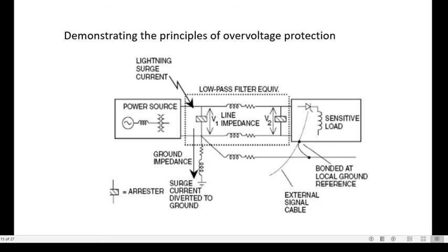So this metal oxide varistor acts as an insulator at a nominal voltage, and at an increased voltage due to lightning, it acts as a conductor, diverting the path towards the ground. So these are the utility surge arrestors. These are the devices to protect the electrical equipment from overvoltage transients caused by external lightning or internal switching events. This device is used to protect the equipment in power transmission and distribution systems from the utility side. Okay. So this is all about the lightning arrestor.